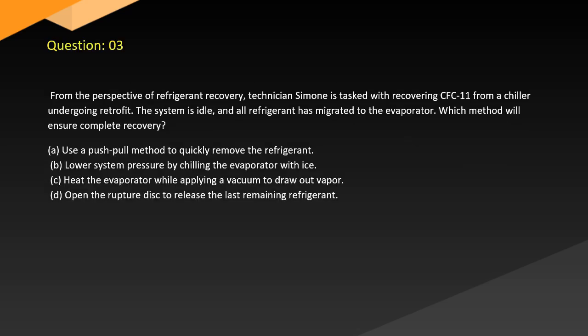Question 3. From the perspective of refrigerant recovery, technician Simone is tasked with recovering CFC-11 from a chiller undergoing retrofit. The system is idle, and all refrigerant has migrated to the evaporator. Which method will ensure complete recovery? A. Use the push-pull method to quickly remove the refrigerant. B. Lower system pressure by chilling the evaporator with ice. C. Heat the evaporator while applying a vacuum to draw out vapor. D. Open the rupture disc to release the last remaining refrigerant.